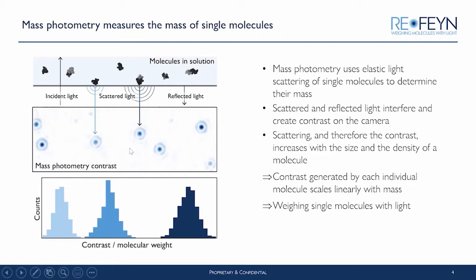More specifically, it is the interferometric analysis of the light scattered by molecules in solution that makes it possible to determine the mass. Three components contribute to image formation: light reflected from the glass-water interface, the light scattered by molecules in solution — whether a protein, lipid, or nucleic acid — and the interference between the scattered and reflected light. This interferometric signal is proportional to the mass of molecules, and every detected event is counted to generate a histogram giving a mass distribution of all biomolecules in solution.